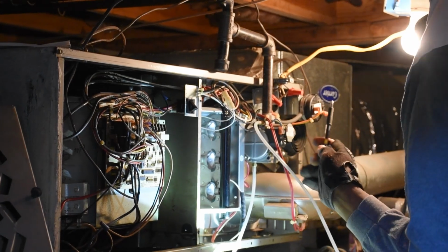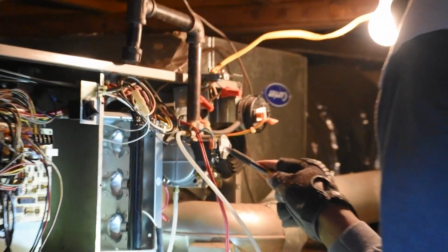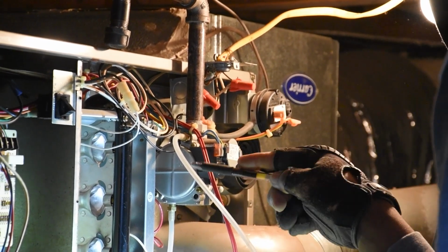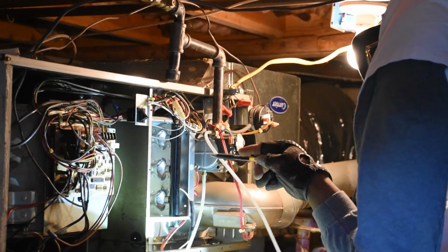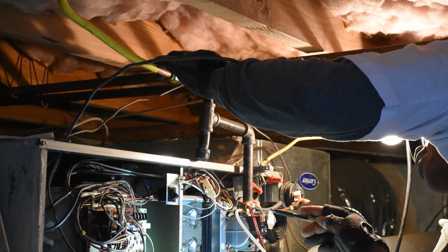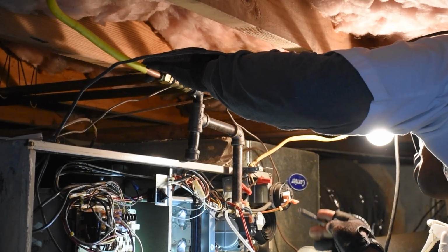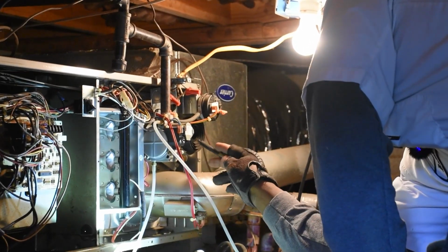And as you go over, this component is the gas valve. This is what controls the flow of the fuel as it goes in to create the combustion in the heat exchanger. This is a shutoff, so as the gas flows in, this is a safety. This interrupts the flow of the gas, whether you want it or not. If you have to service the gas valve, you have to be able to isolate the fuel from the system itself.